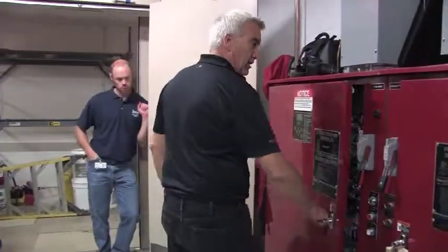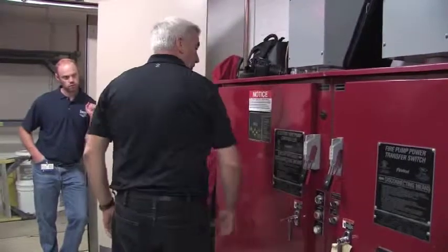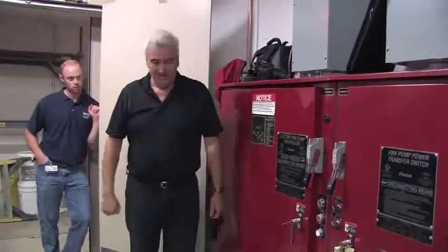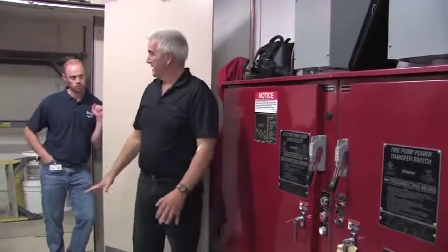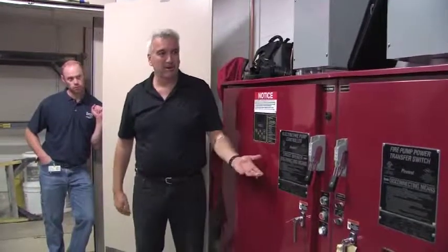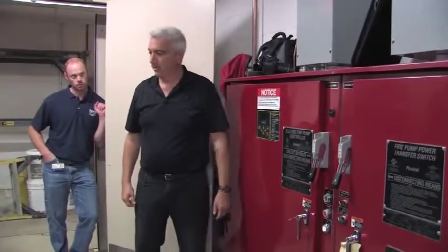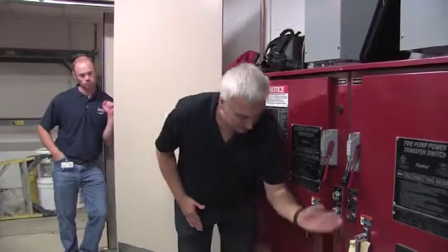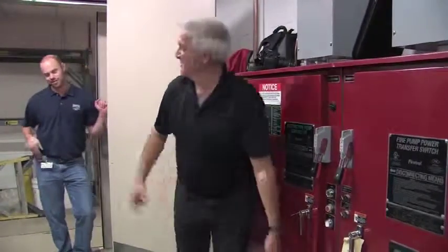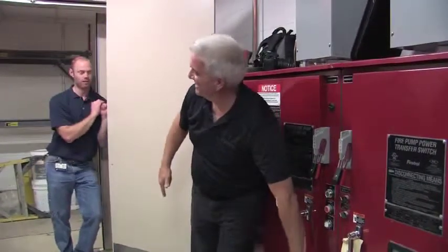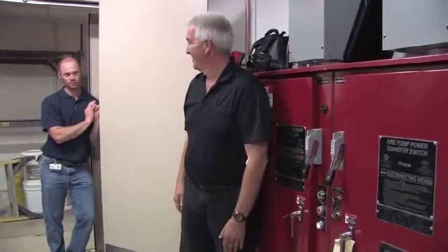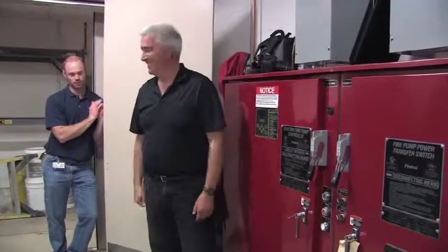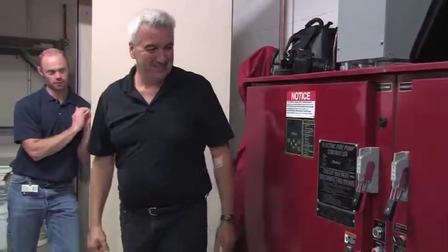I've seen times when I've gone into not well-kept pump rooms in facilities that don't know what they're looking at inside their buildings, and the guy says the pump stops every now and then all by itself. I'll walk into the room, and there's a folding table leaned up against the controller right here. And every time they slam one of the doors, it vibrates slightly and pushes that start button in. No, seriously. So, just gotta be careful.